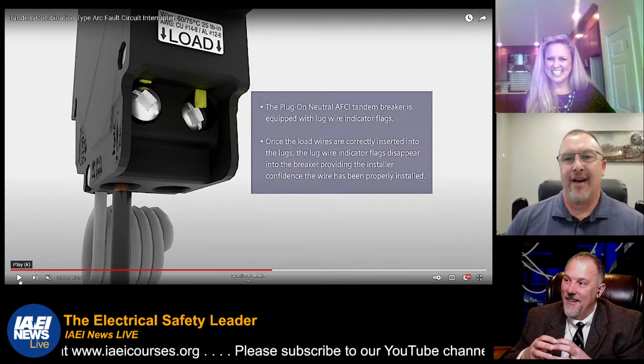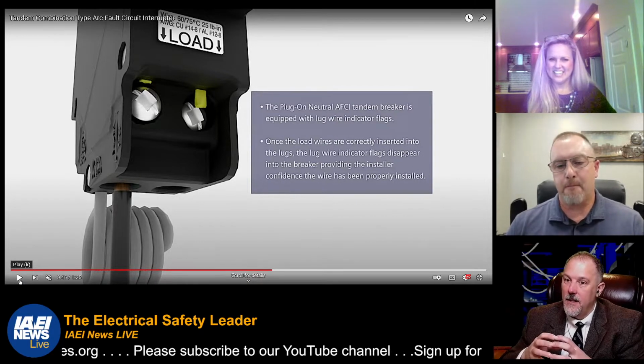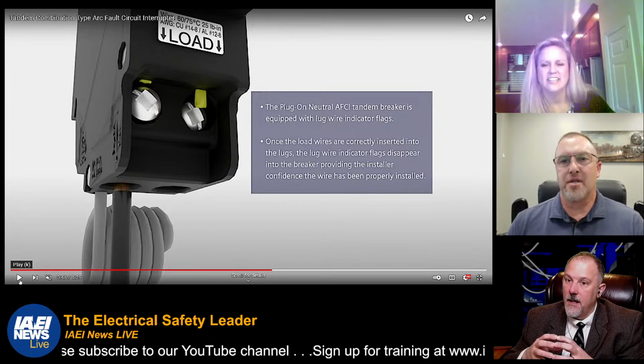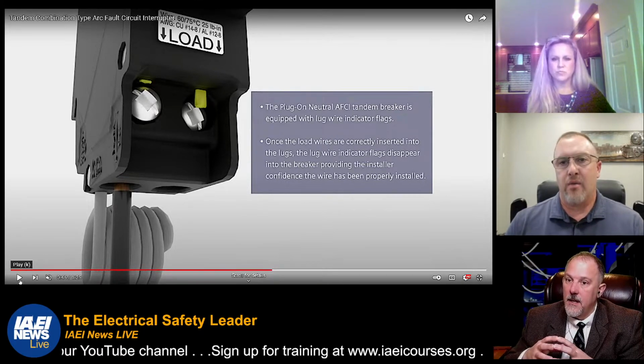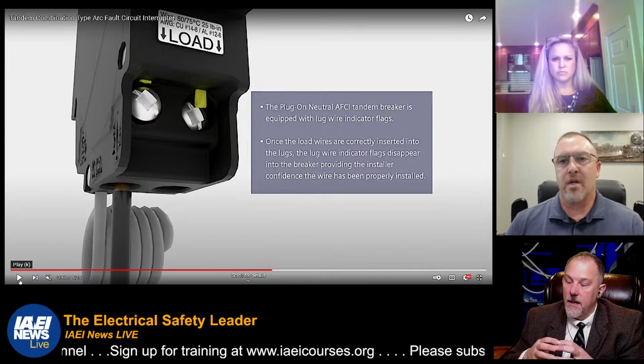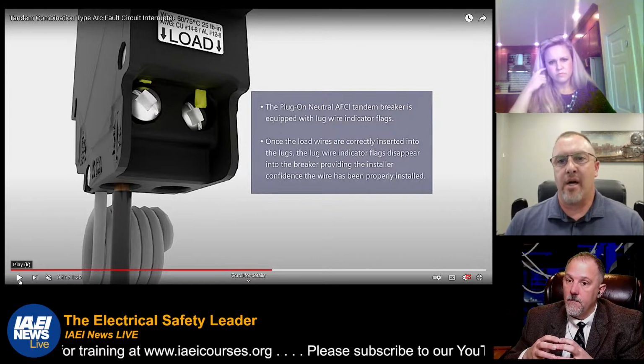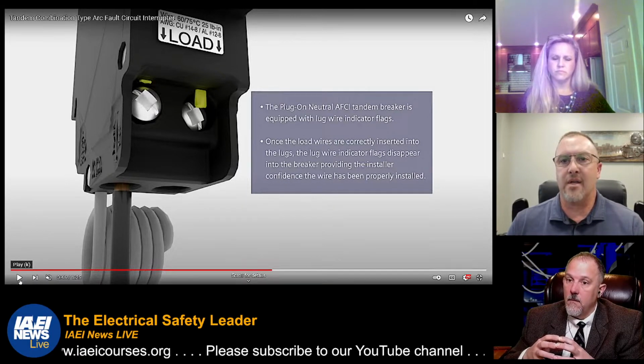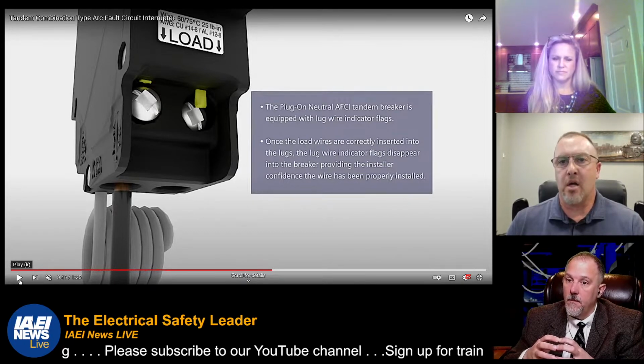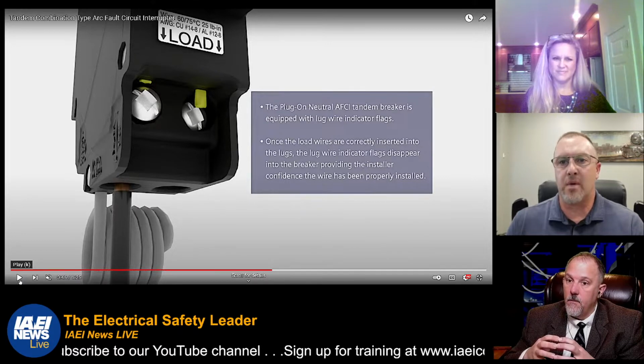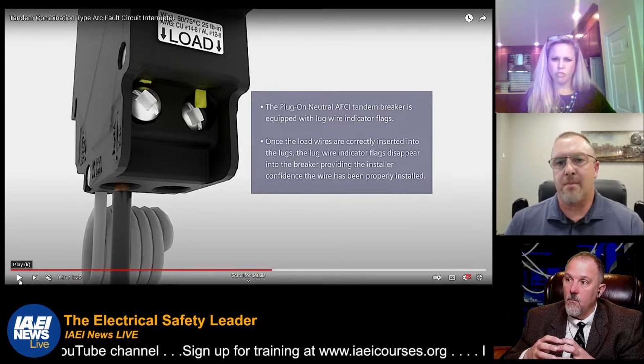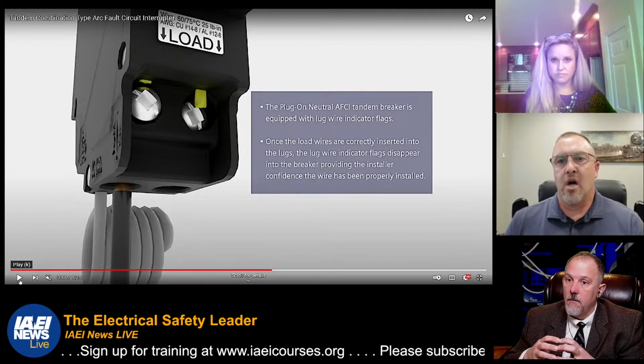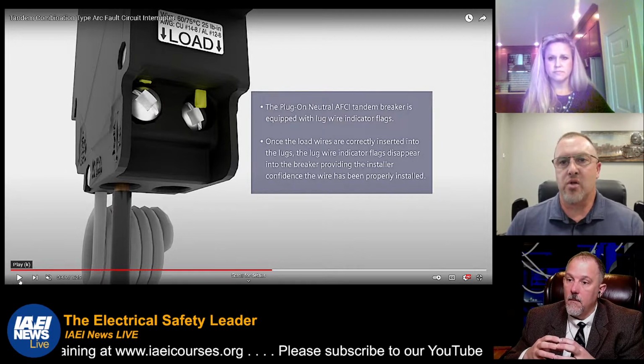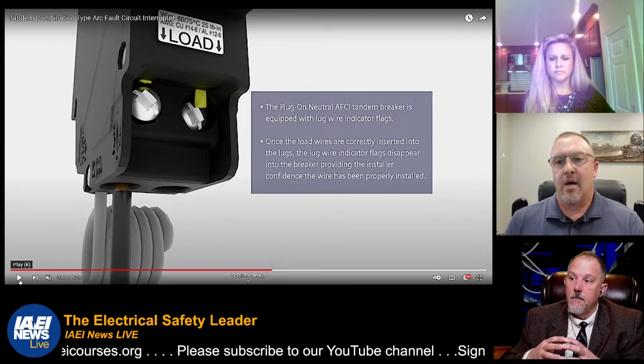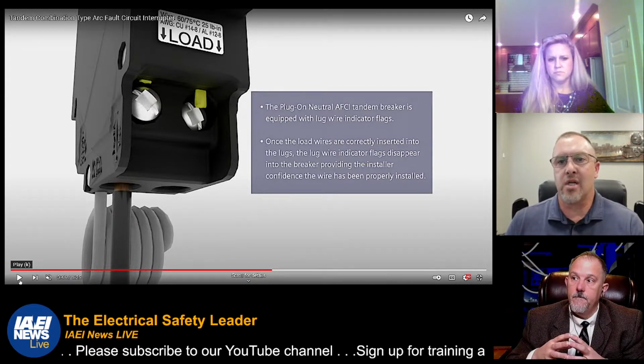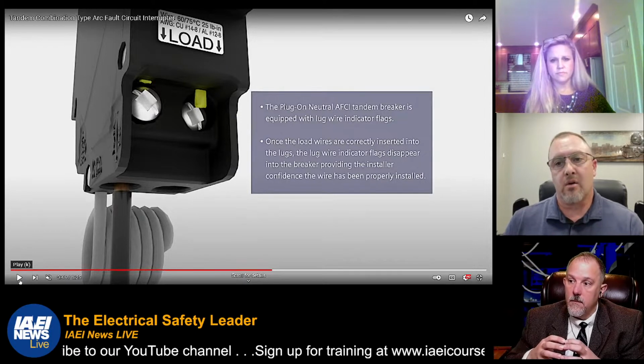I think it's fantastic. This breaker has given us so many solutions to problems that we've had for years. That indicator helps us to know that the wire's in. You can have a wire in, and electricity going across, but you don't have it properly connected to the lug, and then you apply a load to the circuit, and all of a sudden you start getting a problem with that circuit. So from a time and efficiency standpoint when we install, knowing that flag has gone, you can do a visual check to know that the wire is installed where it needs to be. We're not going to have any issues with loose wires or wires not making connection in that lug. So that's a great thing.